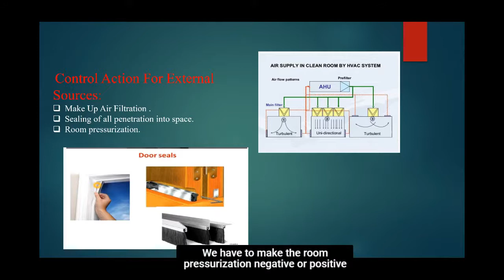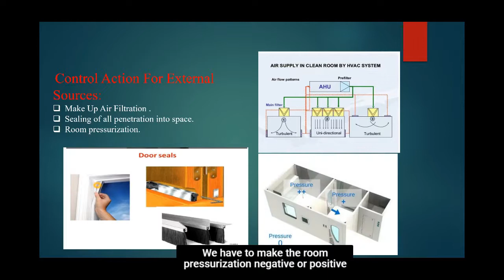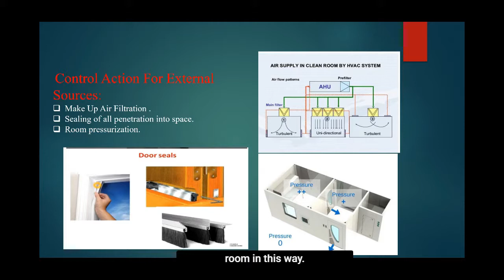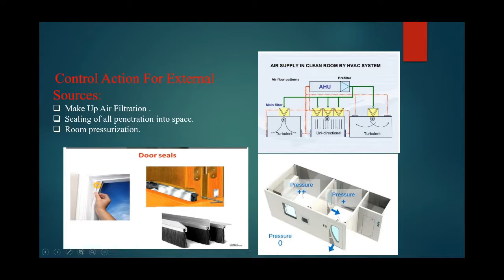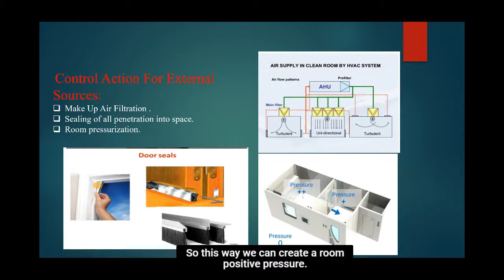The next is room pressurization. Negative or positive room pressure is an isolation technique used in hospitals and medical centers to prevent cross-contamination from room to room. By room pressurization, we will not allow surrounding particles to enter inside the room. In this way, we can maintain cleanliness inside the clean room. In this picture, here is 2 positive and here is 1 positive. This 2 positive means air can enter this room, but this air cannot enter this room. Then this air can enter this area because here is 0 pressure. So this way we can create the room positive pressure.